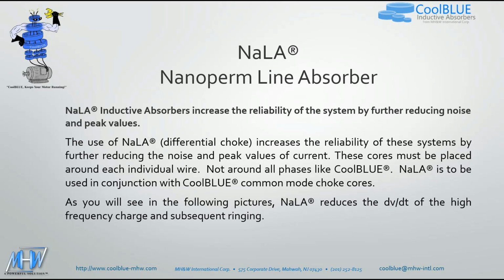So the other product that basically goes along with the CoolBLUE is what we call a NALA, which is a nanoperm line absorber. It's a differential choke that increases the reliability of the system by further reducing the noise and peak values of the current. These cores must be placed around each individual wire, not around all phases like the CoolBLUE. And this NALA is to be used in conjunction with CoolBLUE common mode choke cores. So the solution is really both the NALA and CoolBLUE being used together. As you'll see in the following pictures, NALA reduces the dv/dt of the high frequency charge and subsequent ringing.